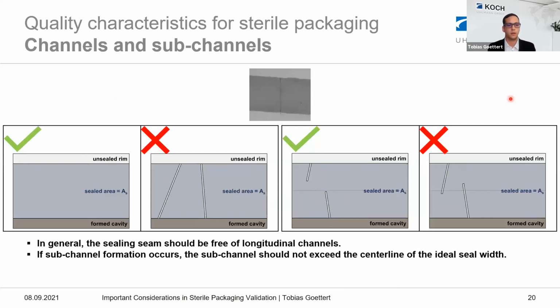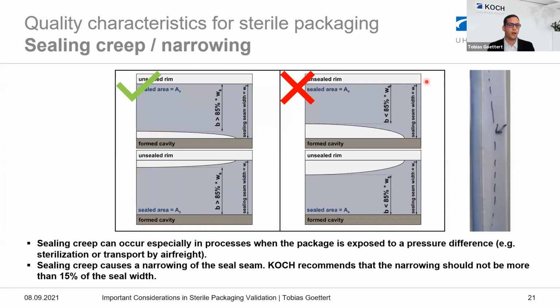The next type of failure will be channels. Your package should be free of channels which go through the whole sealing area, like this. And if you have sub-channels, we recommend they should be not more than half, or above the center line of the sealing area. Another type of failure could be sealing creep, or also narrowing of the sealing seam. This can happen when you expose your package to a pressure difference, like during sterilization, or if your forming process is not good enough. And we recommend not more than 15% of the whole sealing width.